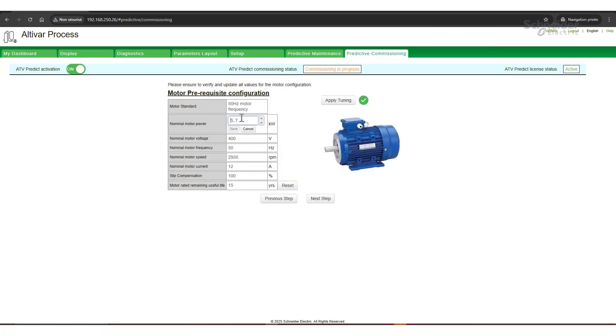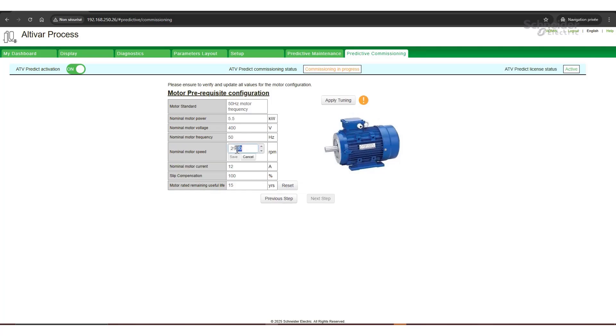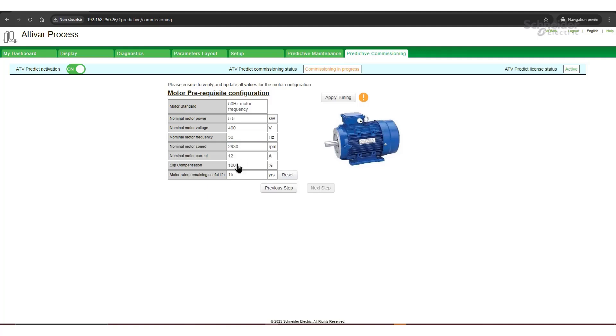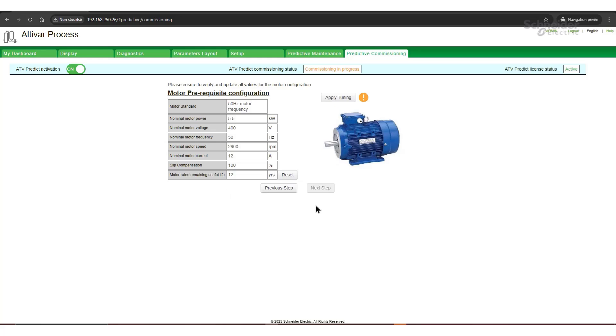Set the motor parameters on the next page. Our motor has 5.5 kW rated power, nominal voltage 400 volts, nominal frequency 50 Hz, and nominal motor speed 2900 revolutions per minute. If needed, we can adjust the motor's rated remaining useful life — let's set it to 12 years. Here we can apply auto-tuning of the motor. When the auto-tuning is complete, the status will change from yellow to green.